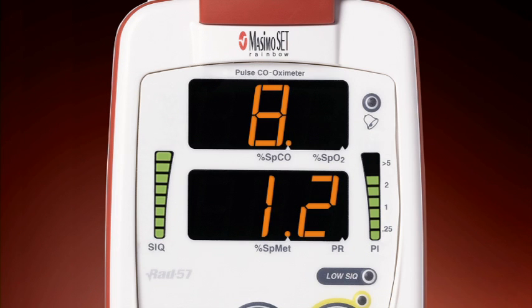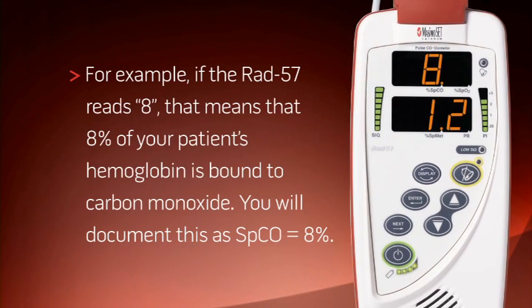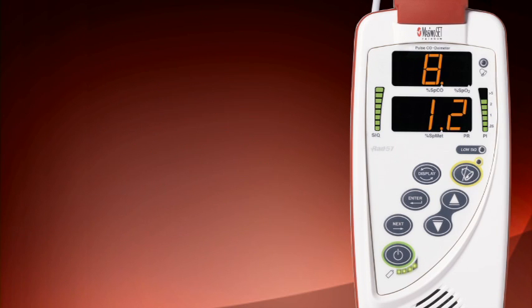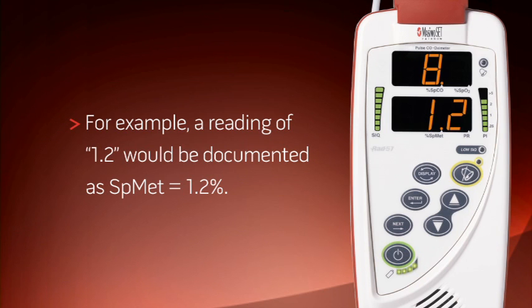The SpCO reading represents the amount of hemoglobin bound to carbon monoxide and is measured as a percentage. So for example, if the Rad57 reads 8, that means that 8% of your patient's hemoglobin is bound to carbon monoxide. You will document this as SpCO equals 8%. Similarly, the SpMet indicates the percent of hemoglobin that is methemoglobin. For example, a reading of 1.2 would be documented as SpMet equals 1.2%.